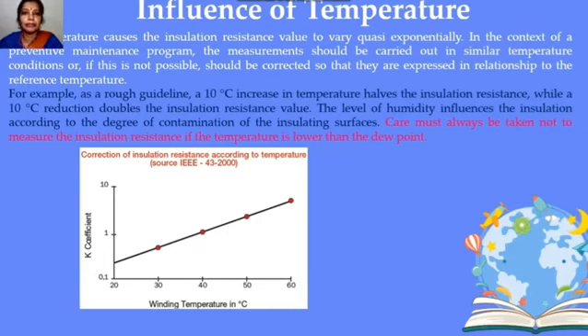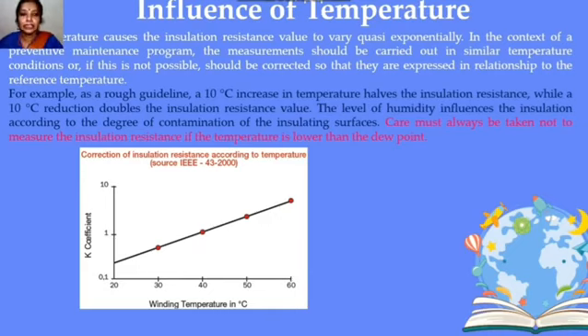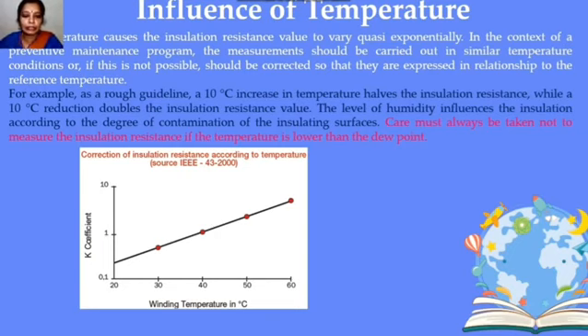Temperature causes insulation resistance to vary quasi-exponentially. Measurements should be carried out at similar temperature conditions; if not, values must be corrected to a reference temperature. As a rough guideline, a 10°C rise in temperature halves the insulation resistance, while a 10°C reduction doubles it. Humidity also affects insulation resistance depending on the degree of contamination on the insulating surface. Care must always be taken not to measure insulation resistance if the temperature is below the dew point. The IEEE Std 43-2000 provides a correction factor K based on winding temperature.